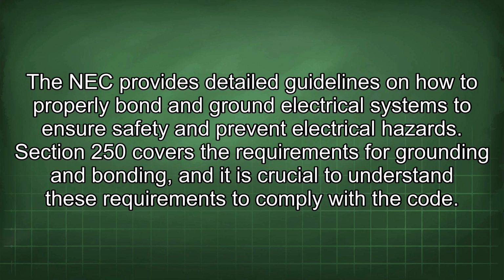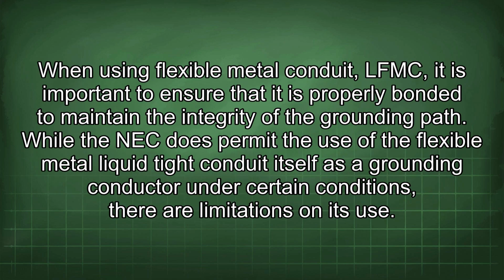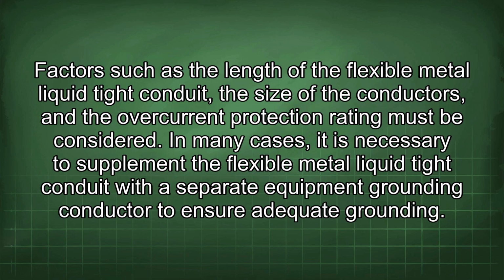The NEC provides detailed guidelines on how to properly bond and ground electrical systems to ensure safety and prevent electrical hazards. Section 250 covers the requirements for grounding and bonding, and it is crucial to understand these requirements to comply with the code. When using flexible metal conduit, LFMC, it is important to ensure that it is properly bonded to maintain the integrity of the grounding path. While the NEC does permit the use of the flexible metal liquid tight conduit itself as a grounding conductor under certain conditions, there are limitations on its use. Factors such as the length of the flexible metal liquid tight conduit, the size of the conductors, and the overcurrent protection rating must be considered.